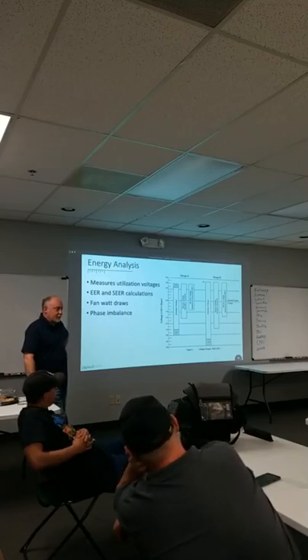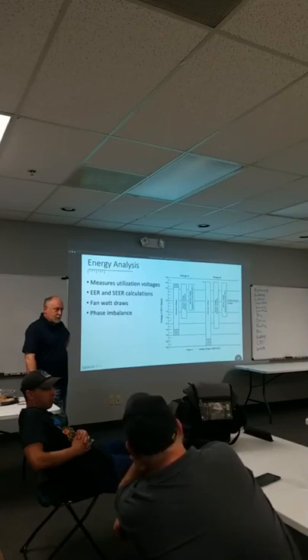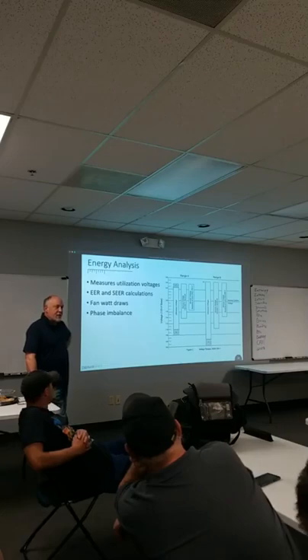A saw might not be the best example because your load's not constant when you're cutting. But based on that, you're saying if voltage goes down, amps go up, right? For motors, yes. On a fixed load, on a three-phase fan, if volts go down, amps go up, right? But it's a fixed load at an approximately same RPM, and the RPM is going to be closer to the 60 hertz. I guess that's where I'm looking at on a fan.